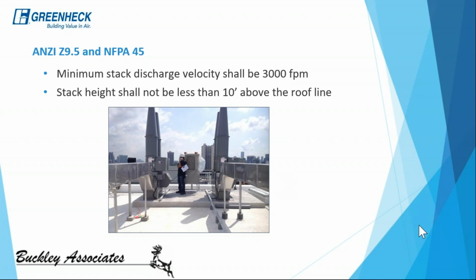And the second code requirement we really need to pay attention to is that the stack height needs to be 10 feet minimum above the roof line. So where this guy's standing here, 10 feet minimum from here to the top of this exhaust fan. Now, remember, these are just minimum requirements. So many times an application may require other design considerations. So for example, are there taller buildings going to be around this space? What is the average wind velocity at the location of this fan? So the climate can change things.